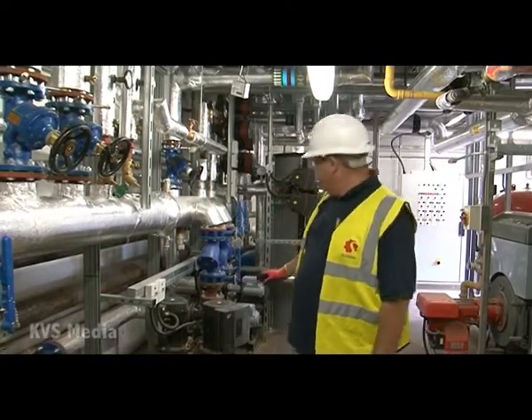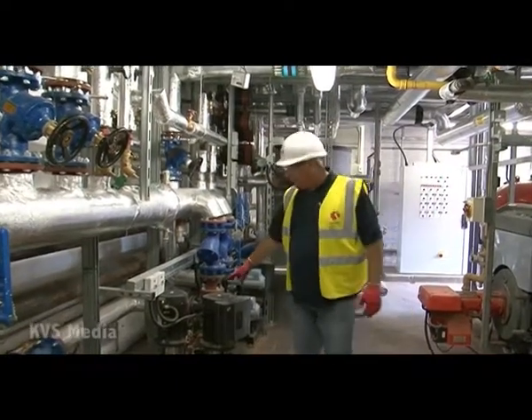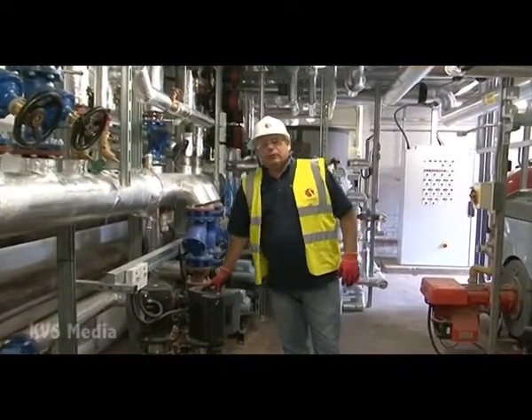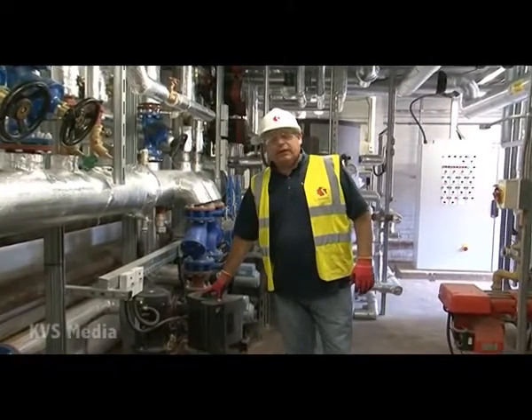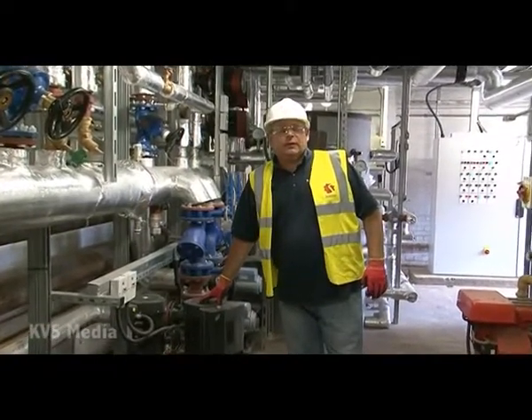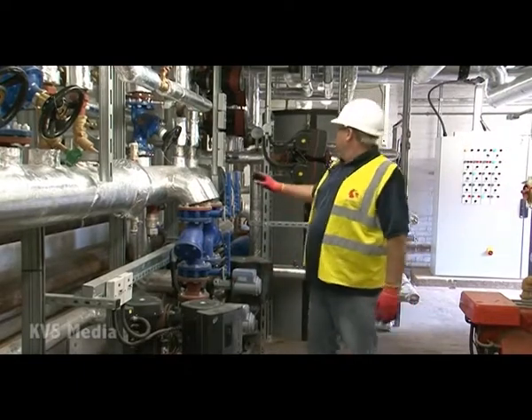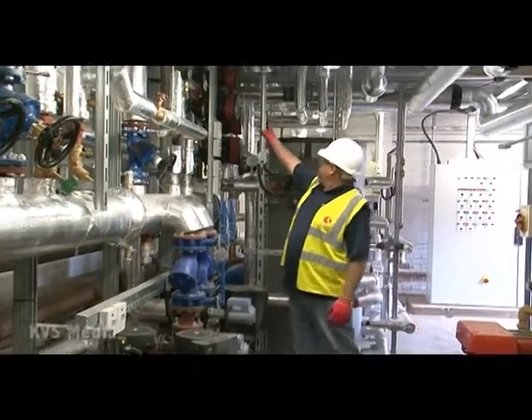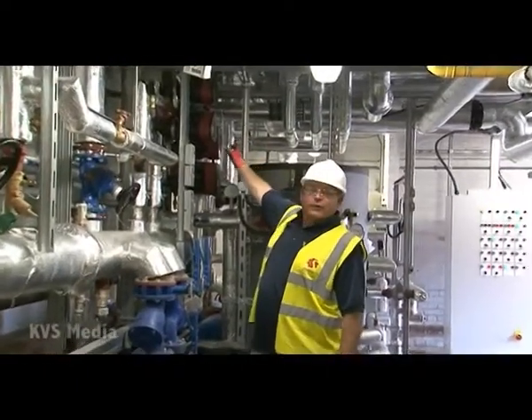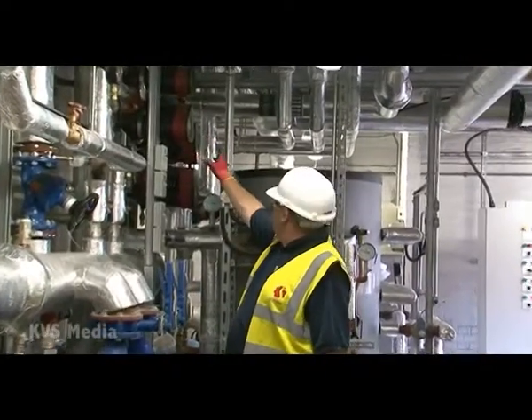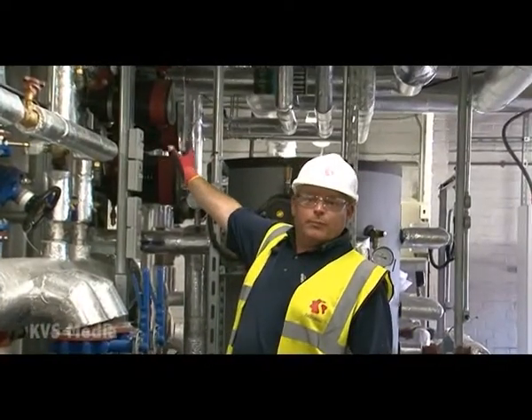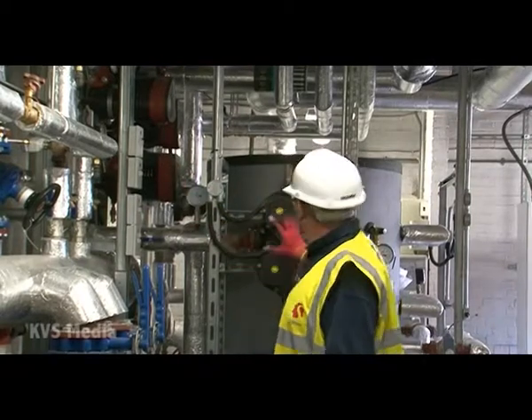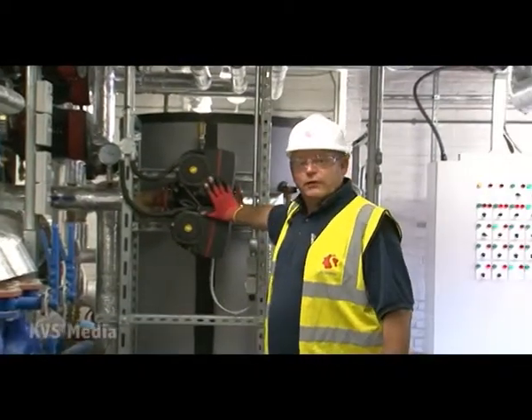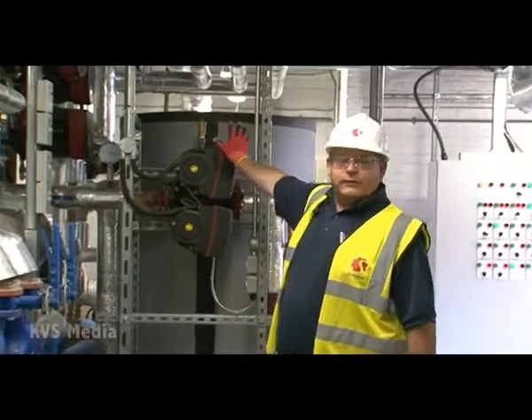Pumps that we've installed. This is the main pumps which feed the new block D and also the underfloor heating systems in the hub. We then go back through, we have the two pumps at the top serve the kitchens, the two pumps below it serve block B. We then have two pumps here which do the hot water. This is the hot water to the two new cylinders.